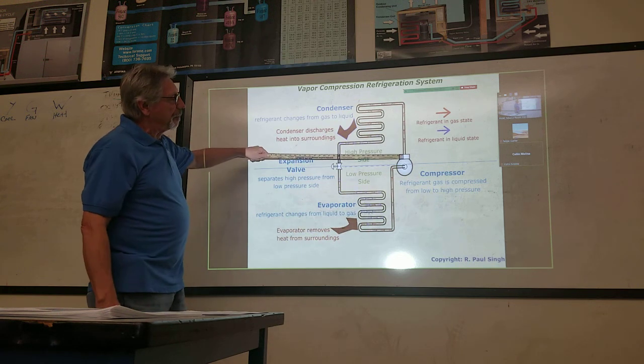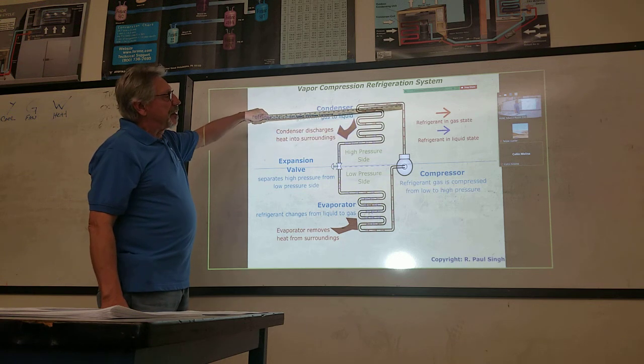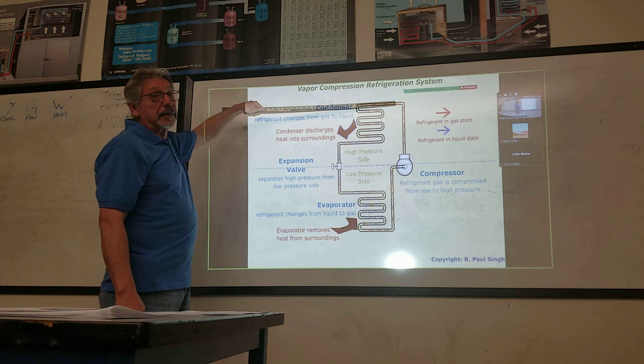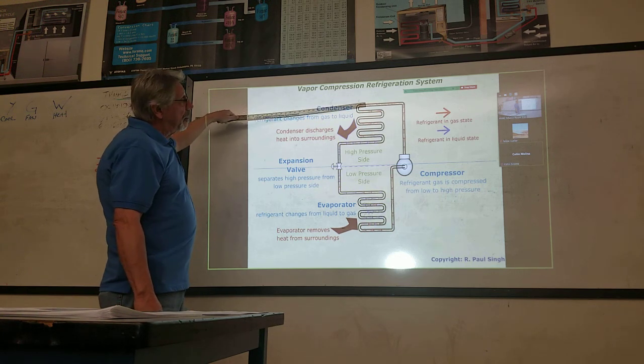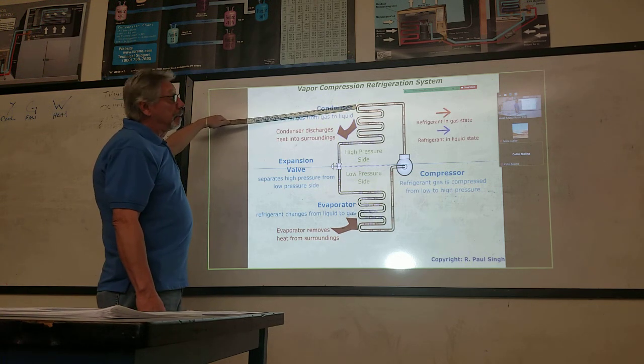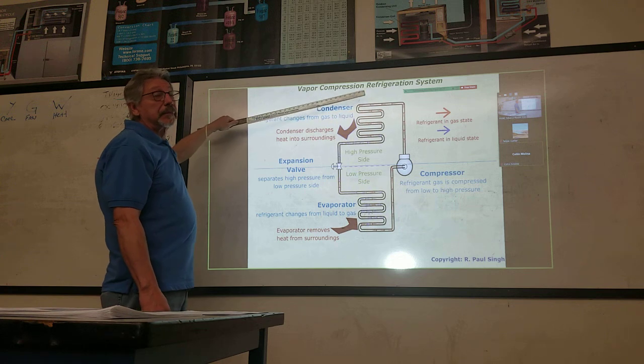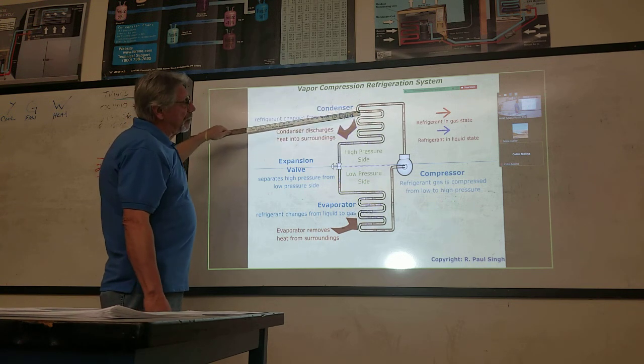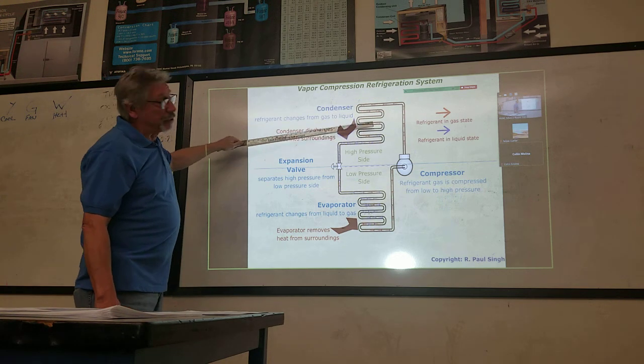As you leave the compressor, this is hot, superheated vapor, about 200 degrees. As it travels through the condenser, it starts to cool off as it rejects the heat.